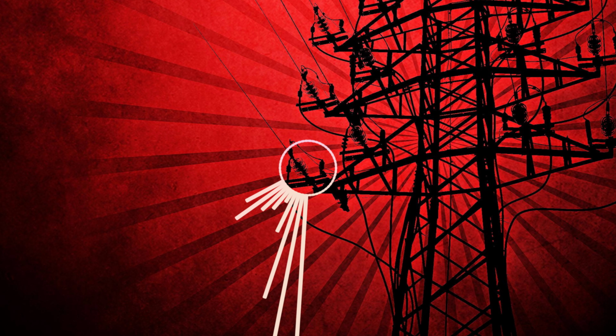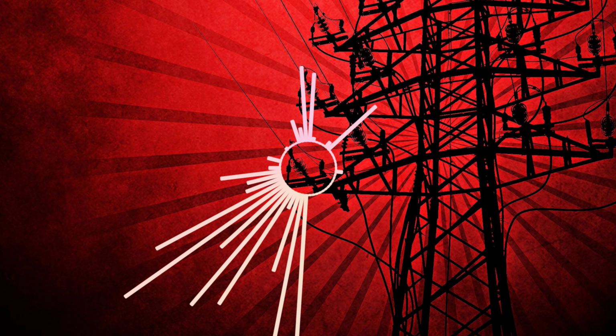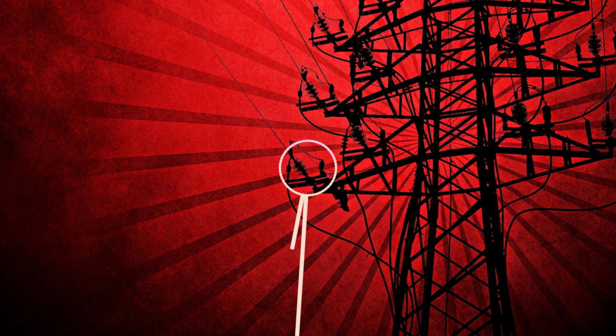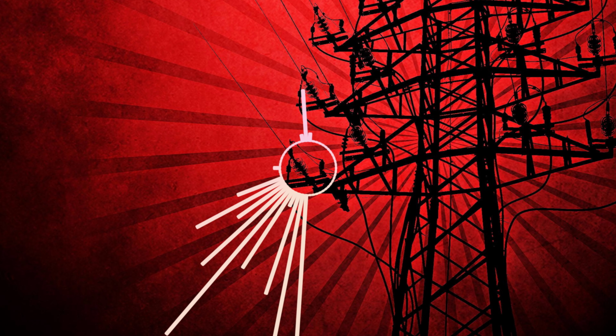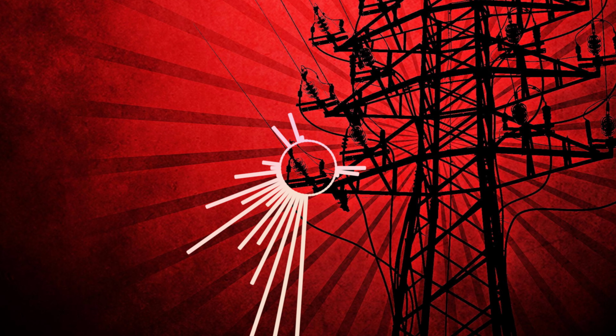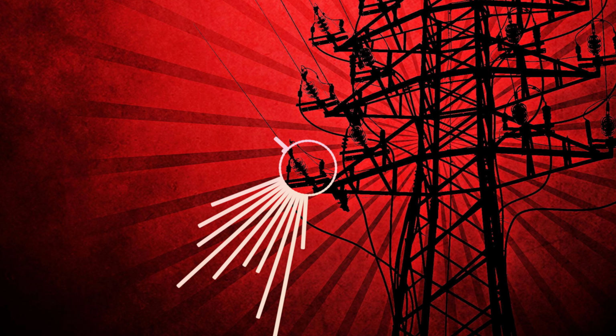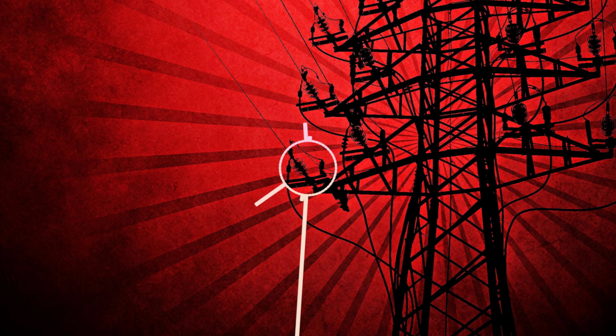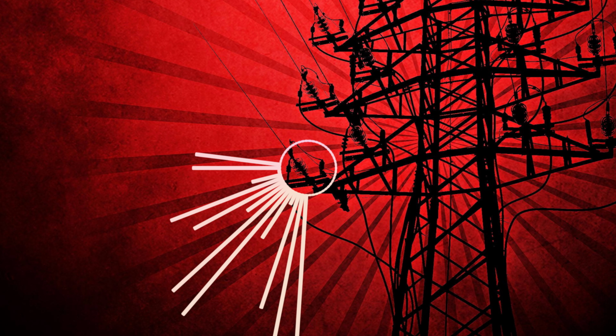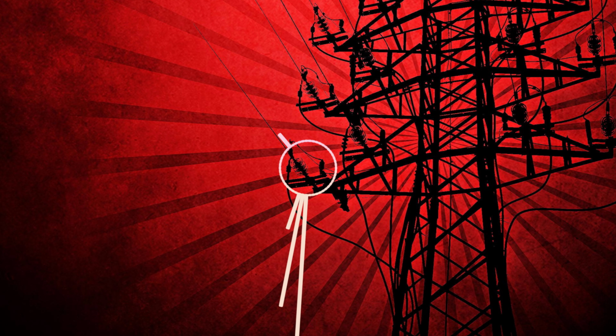For circuits rated 100 amps or less, or for wires between 14 American wire gauge to 1 American wire gauge, you can use wires rated for 60 degrees Celsius. If you use wires rated for higher temperatures like 75 degrees Celsius or 90 degrees Celsius, you must calculate the ampacity based on the 60 degrees Celsius rating of that wire, or based on the wire's actual rating if the equipment is approved for it.